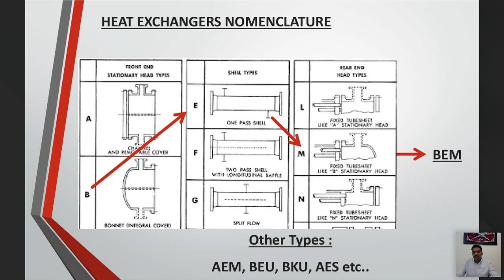This is the typical heat exchanger drawing, where you can find the drawings, and take note that when you do a heat exchanger, the drawing accuracy is very, very important, and it should be very carefully checked before you go for fabrication. Why? After finishing all the fabrication, only at final testing will you come to know the problem. If you know the problem, it is very difficult to solve because the component is already assembled. That's why stage inspection from raw material until the testing is very important in heat exchanger construction.